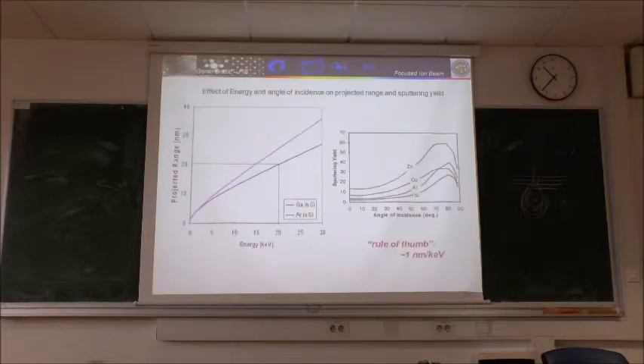What could also be interesting is the effect of energy and angle on the projected range of this volume that interacts. And we can see here for gallium, and the material that we use for sputtering or for examination is silicon, that's that one here. At 30 kilo electron volts, which is the maximum energy of our microscope, we are somewhere around 25 up to 30 nanometers, again using silicon. In gold it will be something like that, in lower Z material slightly larger. But if we lower the energy, this interaction volume would be much smaller.